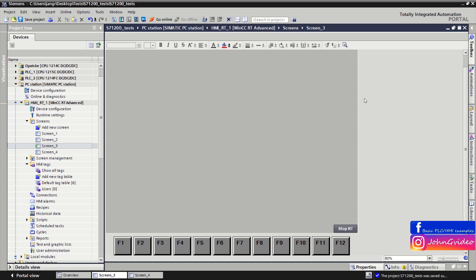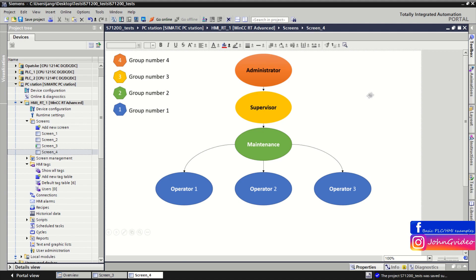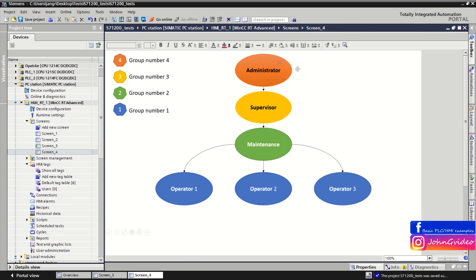Hello, welcome to a video where you can see how to create a basic hierarchy level of users in your HMI project. We have a hierarchy of users — we create six users: the first will be administrator, second supervisor, third maintenance, then operator one, operator two, and operator three. Administrator will be in group number four, supervisor in group number three, maintenance in group number two, and operators in group number one.